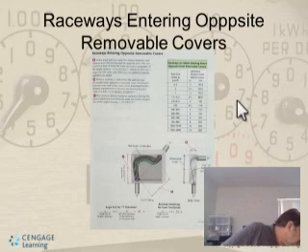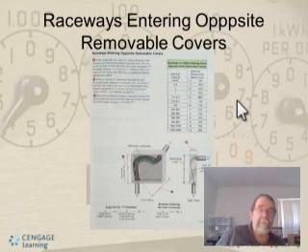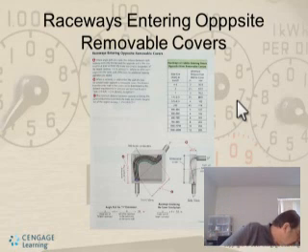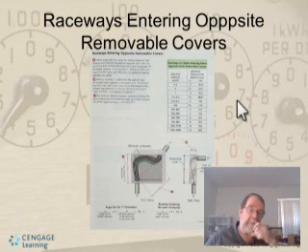Now, coming into raceways entering opposite removable covers, this here is essentially the same thing. You're doing the largest raceway times 6, and so there's no other raceways. Then it's 18. So that's the depth and the height of it, your Y, and then your X, your angle where the box is coming out. The other 2 raceway, coming out of the box is got to be 18 inches diagonal.